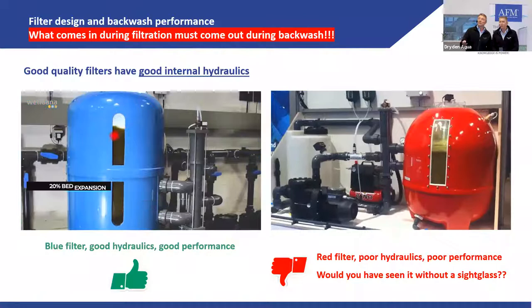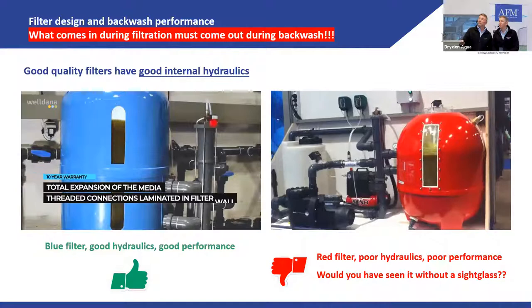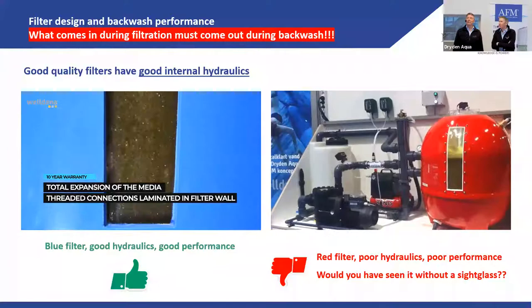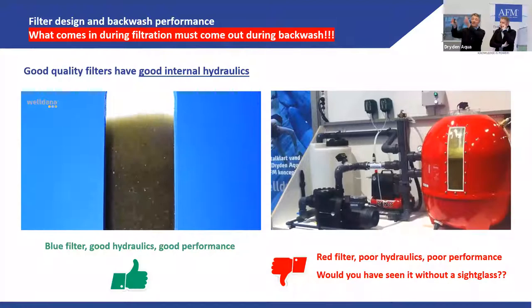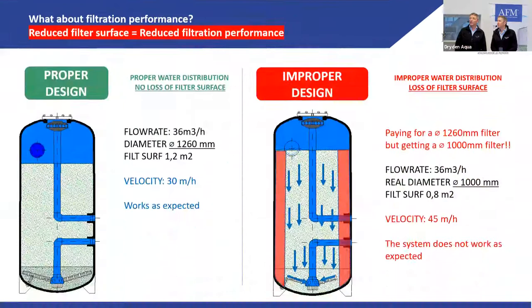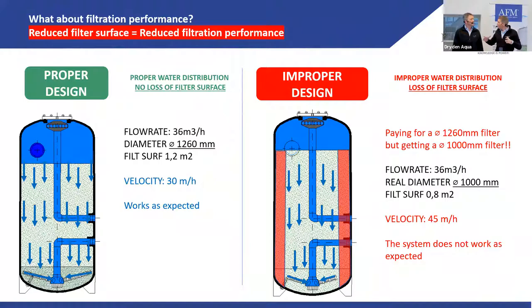A side glass shows whether you have full bed expansion over the entire diameter. These were 600 mm filters with the same pump and Besgo valve. The dead zones in a poorly designed filter reduce the effective filtration surface area. For example, if you lose 10 cm on each side of a 1.2 m filter, the effective surface drops from 1.2 m² to 0.8 m², meaning filtration velocity jumps from 30 to 45 m/hr — a huge difference.